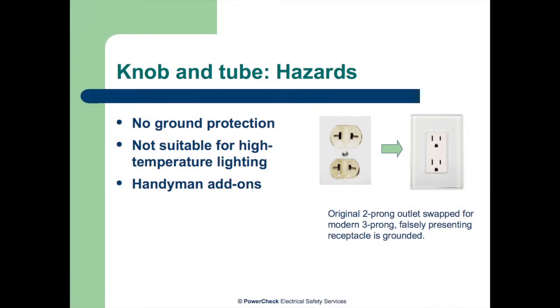Where people have erred is they've taken the two-prong and changed it over for a modern three-prong. Now you can plug in your computer, your power bar, your TV, your entertainment system. But in every one of those cases, the ground is not hooked up. It's just going behind the wall. It's not working. You've got no ground protection. So you've taken a system that was designed for lights and stuff that did not need ground protection, and you've made it into an unsafe system. Hence the peril of knob and tube.